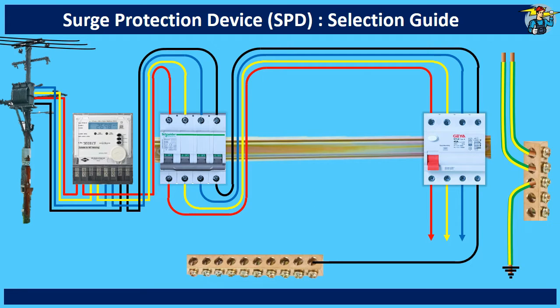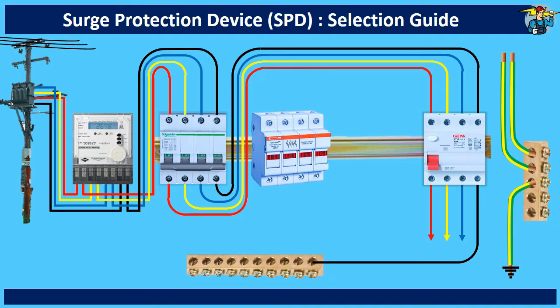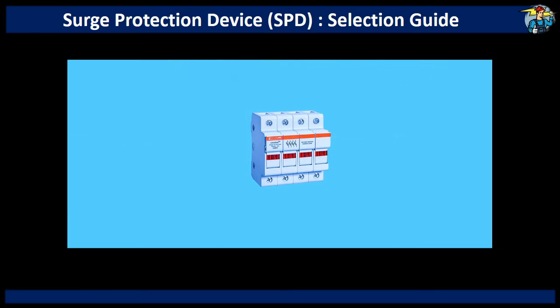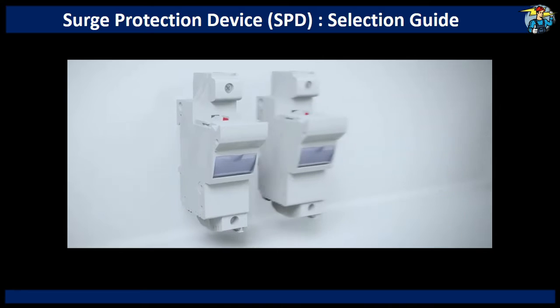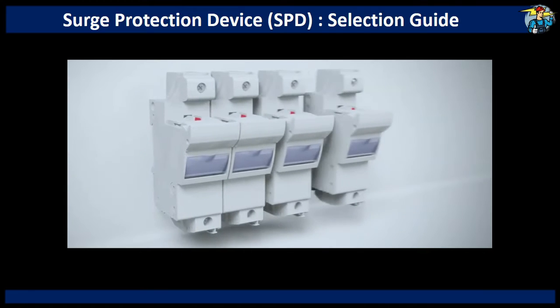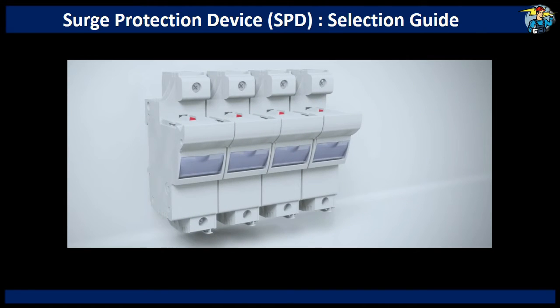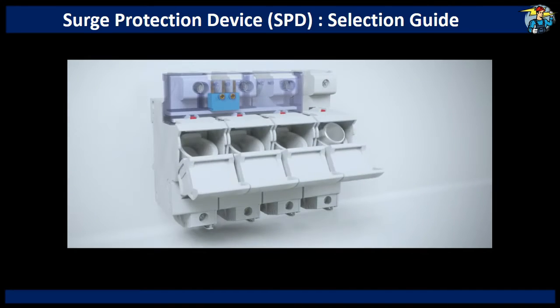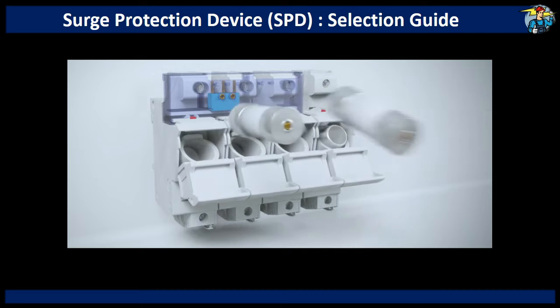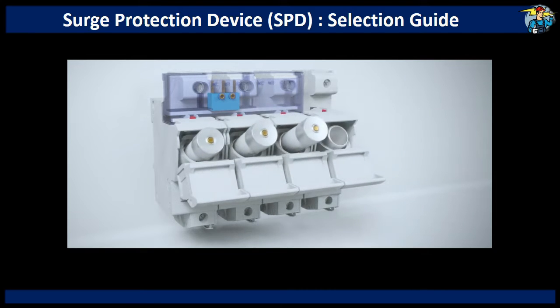Before fixing the SPD, it requires an OCPD — that is an over-current protection device — to be connected in line with the SPD. Typically, this should be a cylindrical fuse holder with the correct rated fuses intact. This is to isolate the SPD in the event of a failure, most likely after a direct lightning strike, and will prevent short circuits of the main lines through its damaged or strained internal parts.